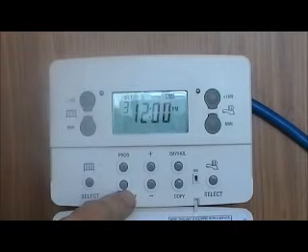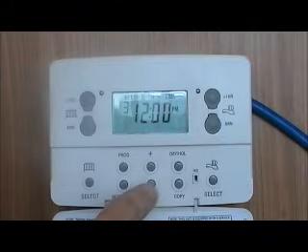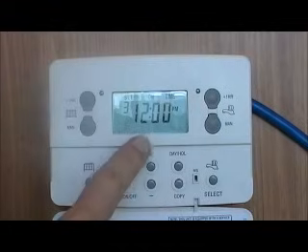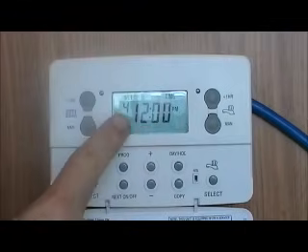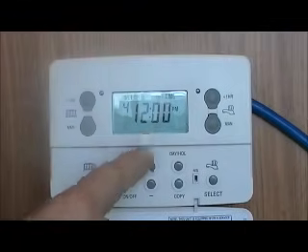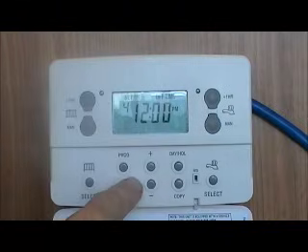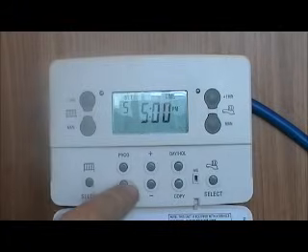This takes you on to the second heating period. This unit is configured to have 3 heating periods per day, but if you only want 2, for example if you don't want one at lunchtime, what you can do is set the on and off times to be the same. So here it's coming on at 12 noon. I'll press next on off. You see the off time, setting number 4, central heating off time, is also noon, so the unit isn't going to come on. Press next on off, and that then takes you to the third heating period.